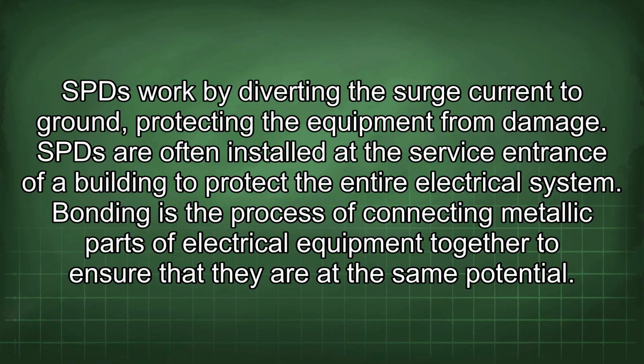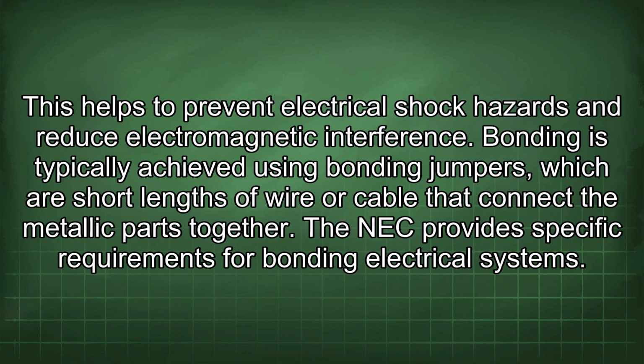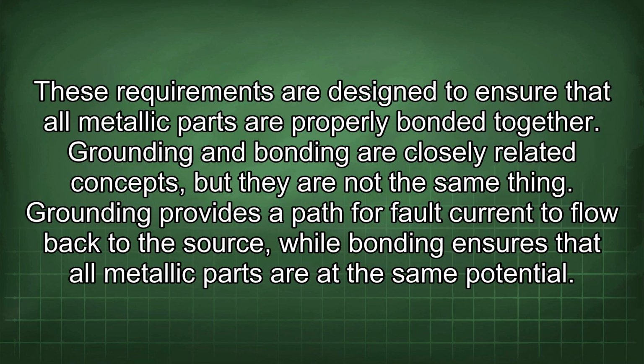Bonding is the process of connecting metallic parts of electrical equipment together to ensure that they are at the same potential. This helps to prevent electrical shock hazards and reduce electromagnetic interference. Bonding is typically achieved using bonding jumpers, which are short lengths of wire or cable that connect the metallic parts together. The NEC provides specific requirements for bonding electrical systems. These requirements are designed to ensure that all metallic parts are properly bonded together.